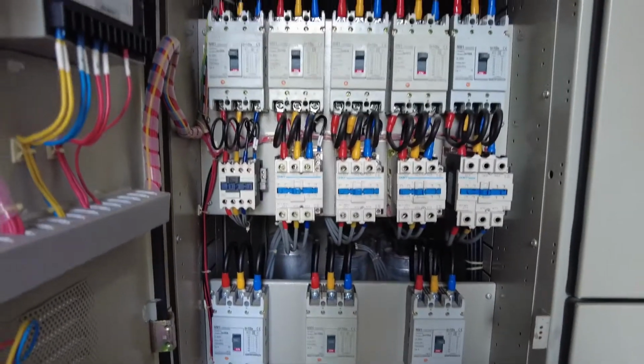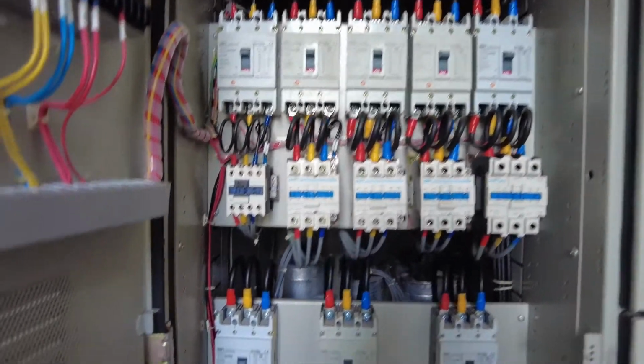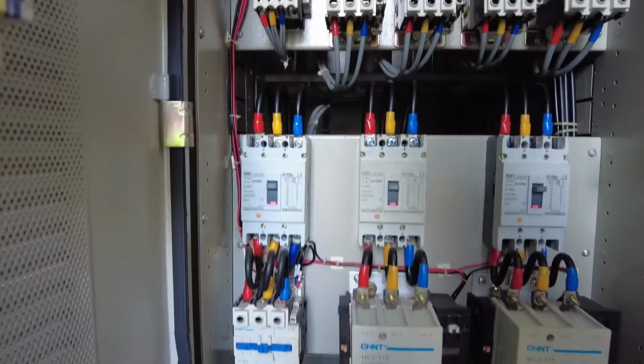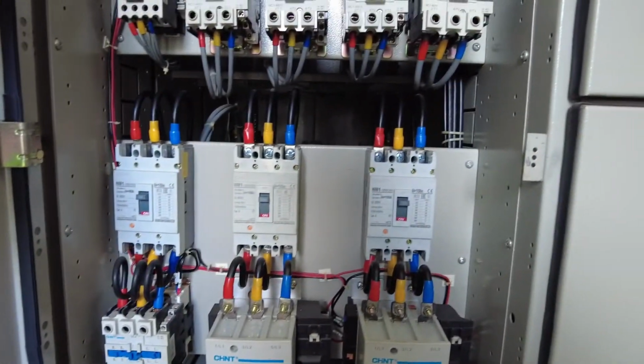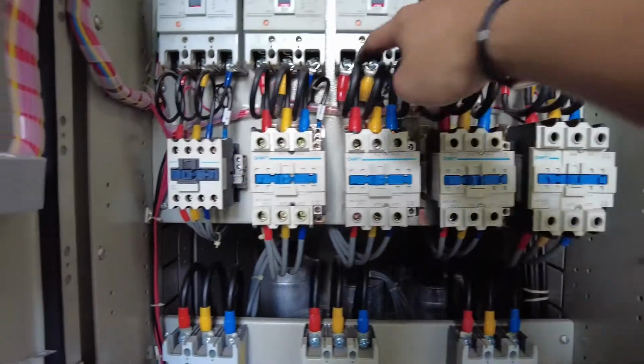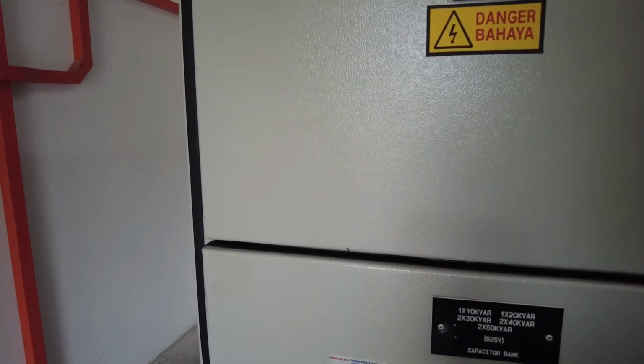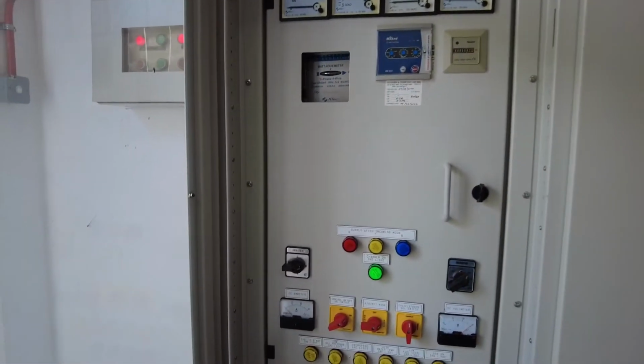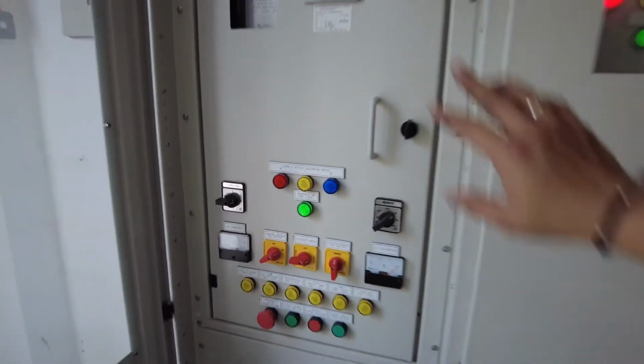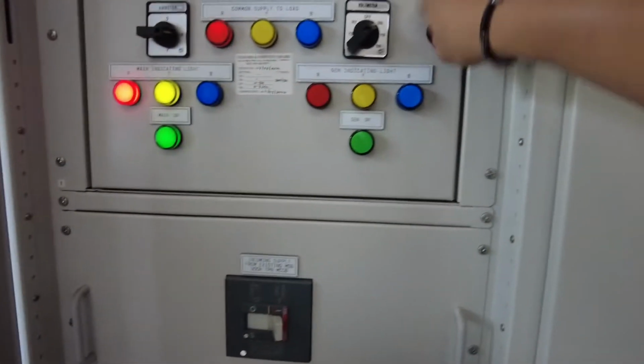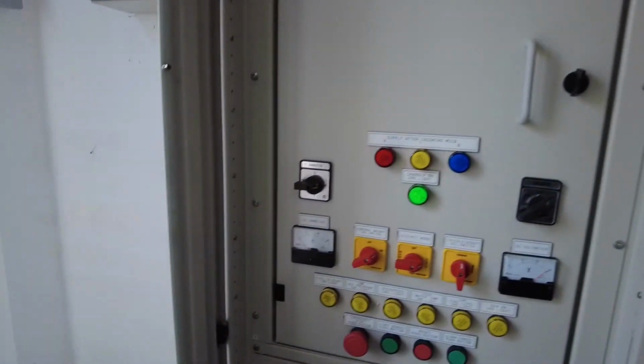Okay, capacitor bank panel, MCCB okay, contactor okay, no contactor jam. Currently no step going in because the load is low. No cable burn. All cable okay. Okay, here we have the Genset AMF panel. Currently the Genset is not running, so it's under off status. This is the Genset ATS panel. Same as previous. We're going to test manual mode first.